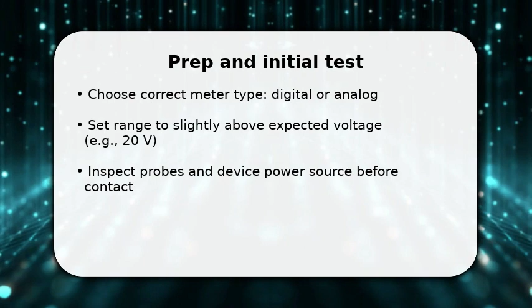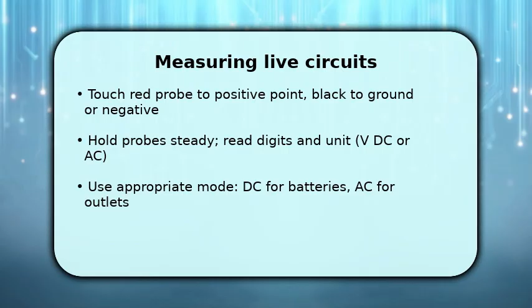You now measure the live voltage. Select DC or AC mode depending on the source because the waveform matters to the reading. With the device powered, touch the red probe to the positive terminal and the black to ground or negative. Hold steady to avoid fluctuating digits. Once connected, observe the numeric value and unit, VDC or VAC, and note polarity if present. If the display bounces, increase the range or enable a hold/averaging feature to stabilize the readout.